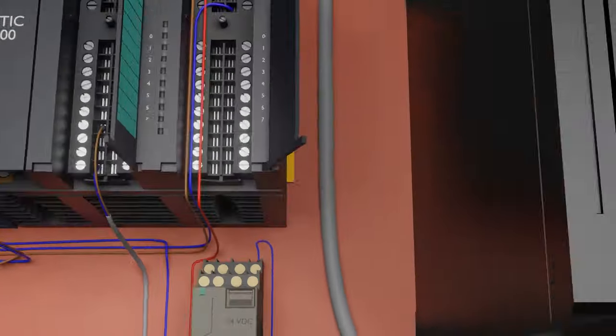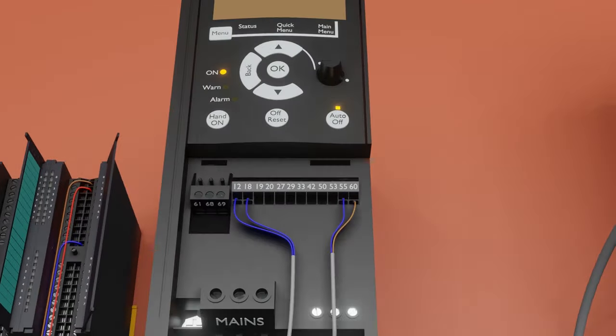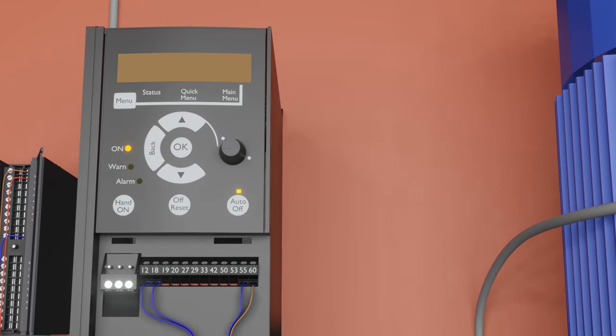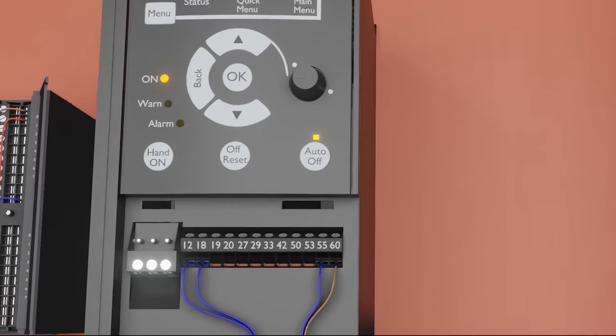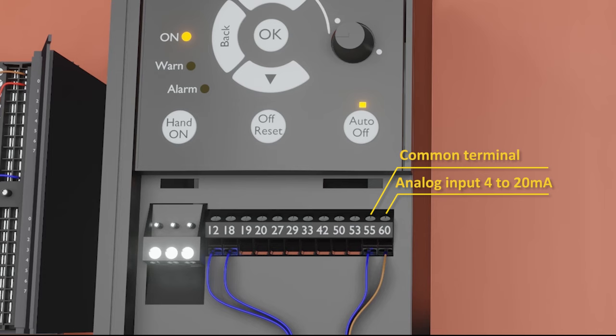Next we have a Danfoss VFD. We will connect the analog output signal from the PLC to the analog input terminal of the VFD as a speed reference. Terminal number 60 is the analog current input of the VFD, and terminal 55 is the common terminal for this analog input.